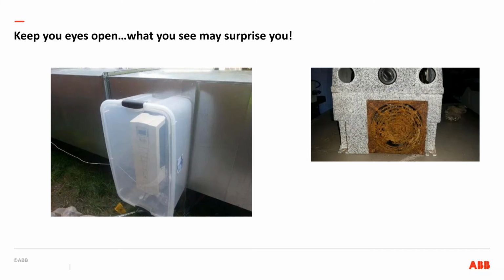I talked earlier about using variable frequency drives on pumps, and you really need to be looking at everywhere we have pumps. We have pumps in our wastewater plants and our water plants. We have them as water features, in swimming pools and water slides, water parks and fountains. We also have them in chilled water loops and heating loops in buildings, and in booster systems and fire systems and all those kinds of things. So this was one where they mounted the variable frequency drive in the pool pump room, and the guy running the facility put open containers of chlorine tablets and muriatic acid in the room, and it caused corrosion. First of all, you can't do that. That's a violation of code, putting chemicals in there, because you've got electricity and a lot of things in there that could cause a failure or an explosion. But it also does damage to the equipment.